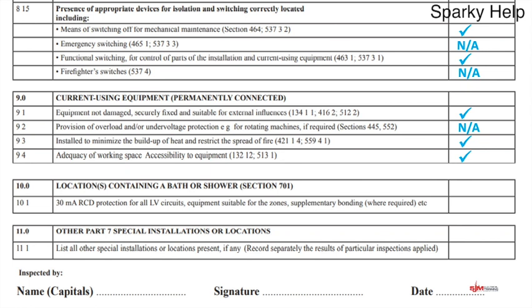Locations containing a bath or shower — most houses have a bath or shower. If they do, you'll probably have an RCD for the low voltage circuits, equipment suitable for zones, and supplementary bonding where required. If you look at the regulations, if you put an RCD in you may not need the supplementary bonding. If you have a bathroom, it's going to be a tick.